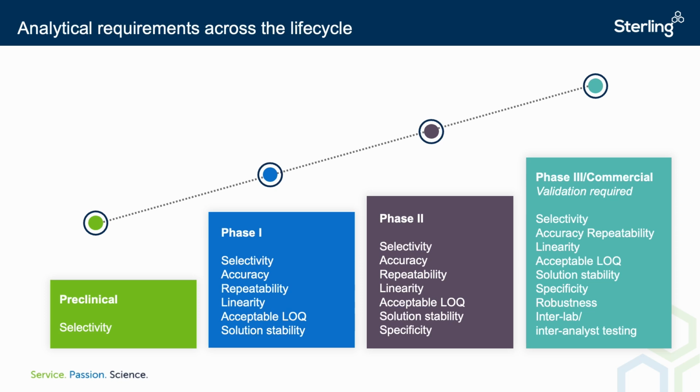In phase 2, accuracy, selectivity, precision, and linearity are required to be evaluated, and the additional factor is specificity. This has to do with the matrix and other contents in the sample. As we mentioned in our previous example, the sample matrix can have an effect on the results of the method by generating background noise or additional impurity peaks that cannot be attributed to the analyte.